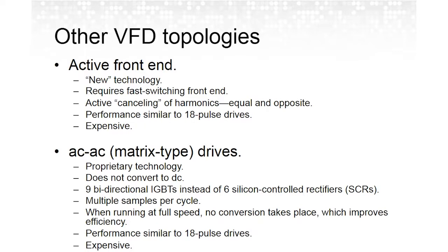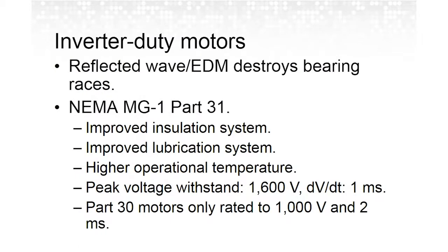The total harmonic distortion associated with these designs is probably somewhere in the neighborhood of about 8%. So it is very comparable to what we expect to see out of an 18-pulse drive. However, they're unusually expensive, just because there isn't that much market penetration. It is assumed that the price will go down as they gain additional acceptance and we see more of them delivered to the field.